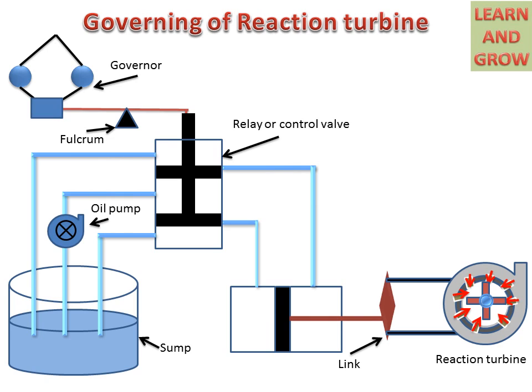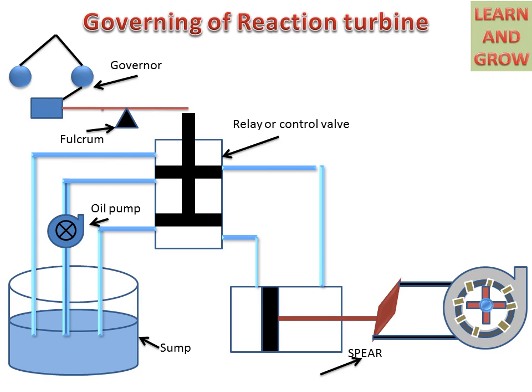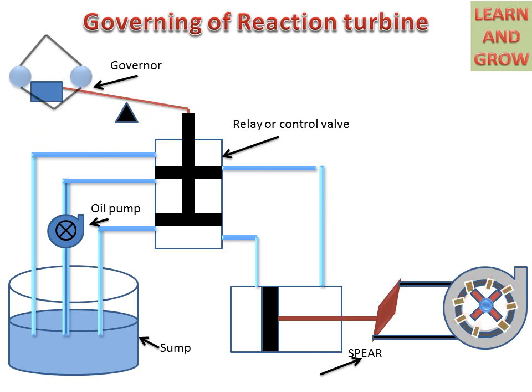Now we see the working of the governing of the reaction turbine. When water enters through the guide vanes and goes to the rotor, the rotor starts rotating. If the load is less, the speed of the rotor will be high. This rotor or turbine is connected to the governor through a linkage mechanism, so the governor rotates at higher speed. Due to the higher speed of the governor, the sleeve will move in the upward direction, pulling the lever and pushing the piston in the downward direction.